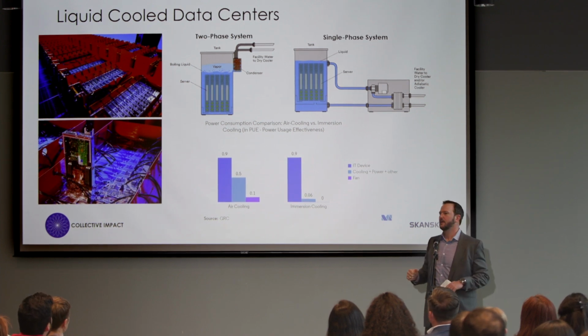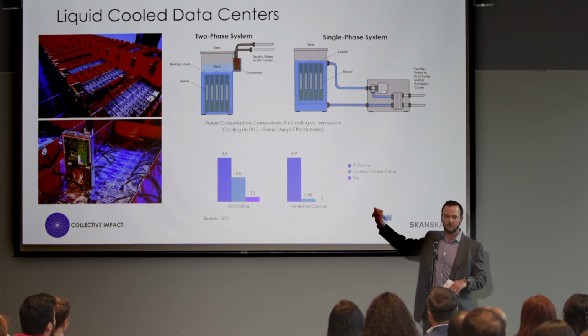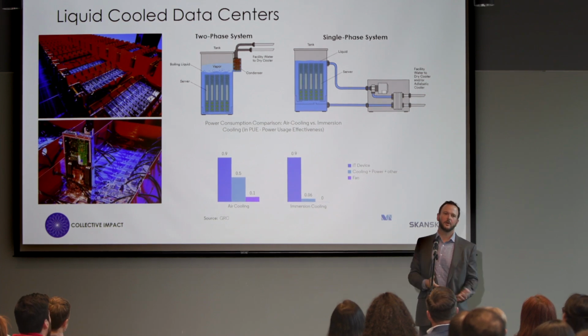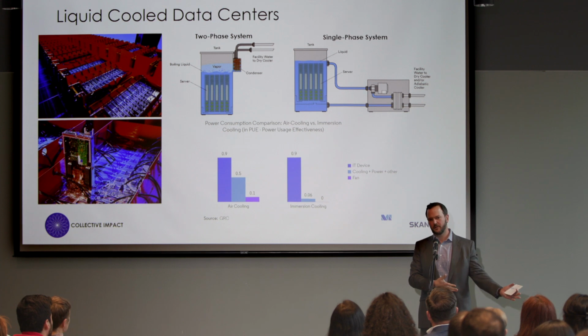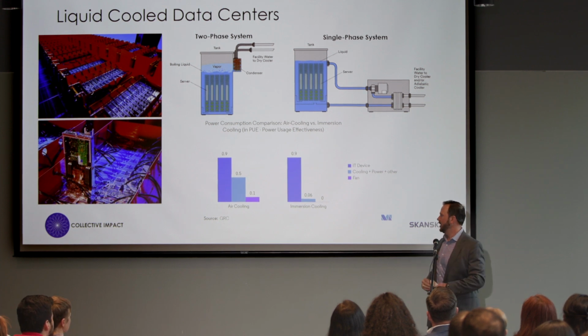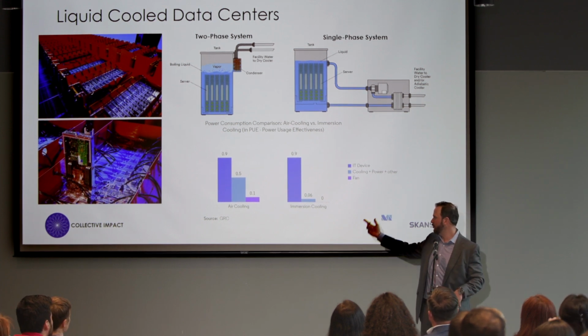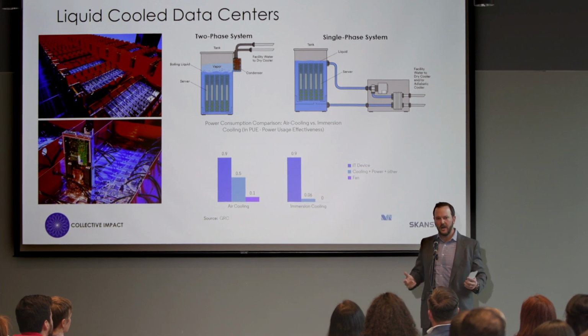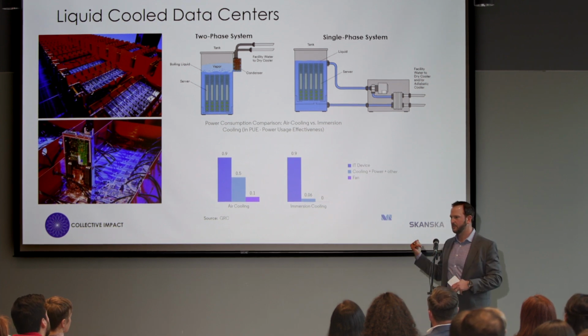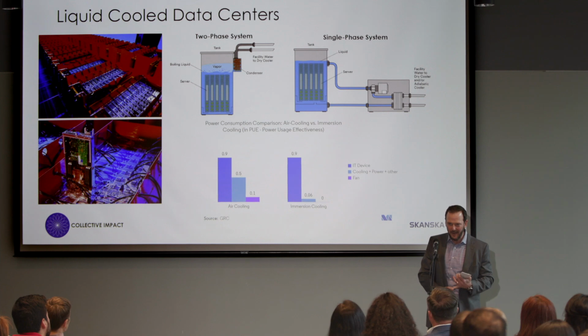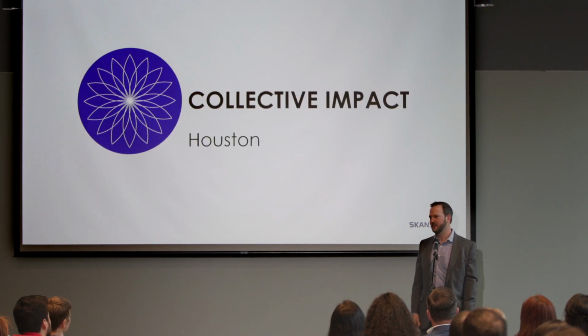It's quiet. All that heat energy comes back out through the oil to another water system, which goes out of the building to a chiller or a dry cooler. We're seeing PUEs of around 1 versus 1.5 — a drastic reduction, which will be a huge trend as AI picks up with massive computing needs, along with cloud computing and so forth.